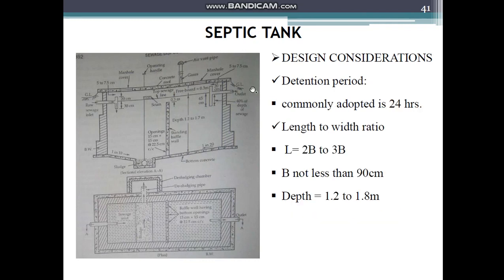More design considerations: the detention period is commonly adopted as 24 hours for easy calculation, or whatever is given in the problem. The length-to-width ratio is L = 2B or 3B. The width B should not be less than 90 centimeters, and depth can be assumed between 1.2 to 1.8 meters.